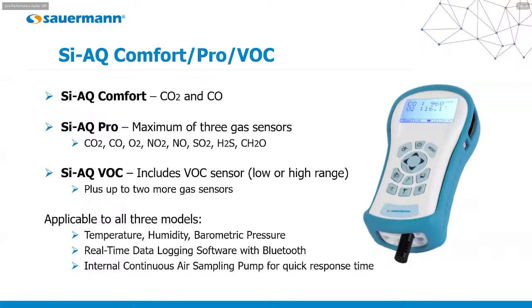Keep in mind, people sometimes confuse CO2 and CO. From an IAQ point of view, they have much different concentrations in a normal, safe, healthy building. For example, CO2 in an occupied space is normally around 500 to 700 or maybe 800 ppm—nothing to be concerned about. Once you get closer to 1,000 ppm or higher, it's more of a concern that you need more fresh air or better ventilation. CO is much different.